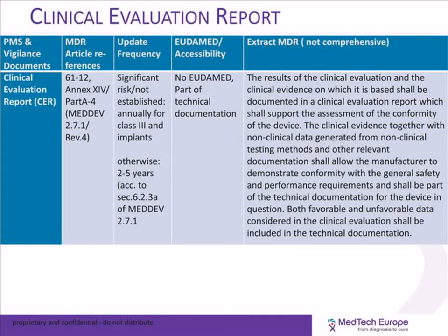So here what you have is the clinical evaluation report. This is the report that supports the conformity assessment, and it needs to include clinical and non-clinical data coming from testing methods, for example, and need to be included in the technical documentation.